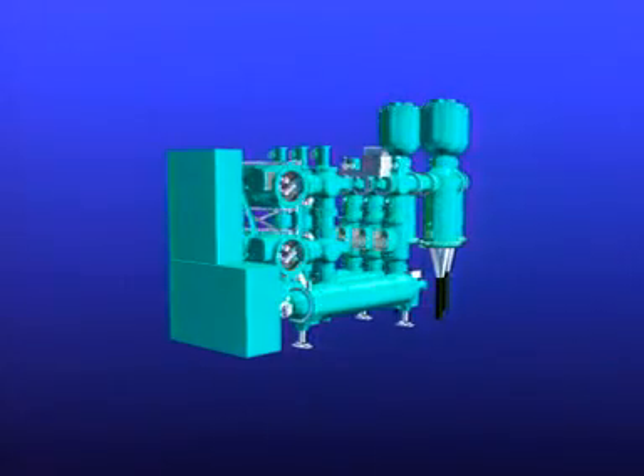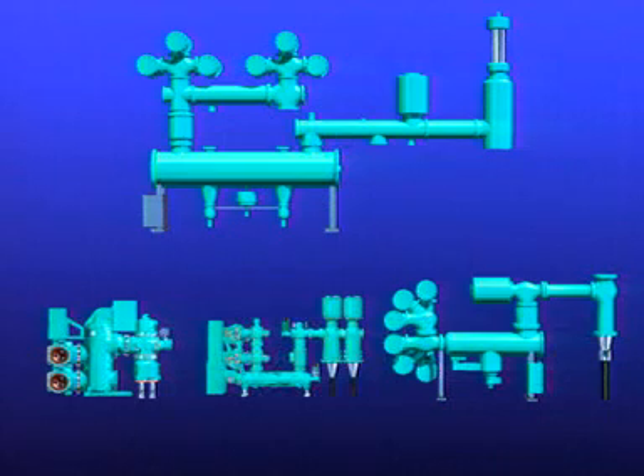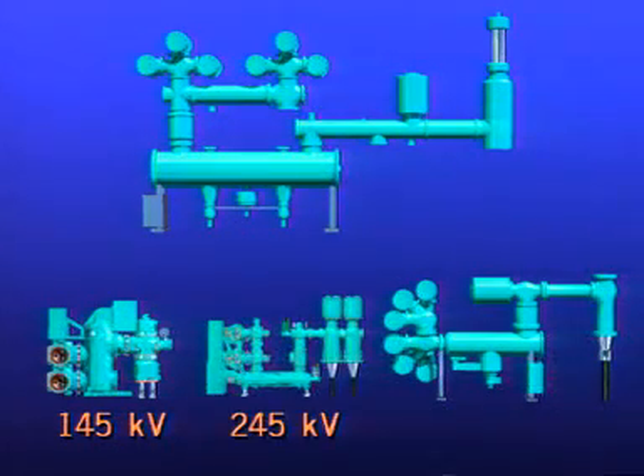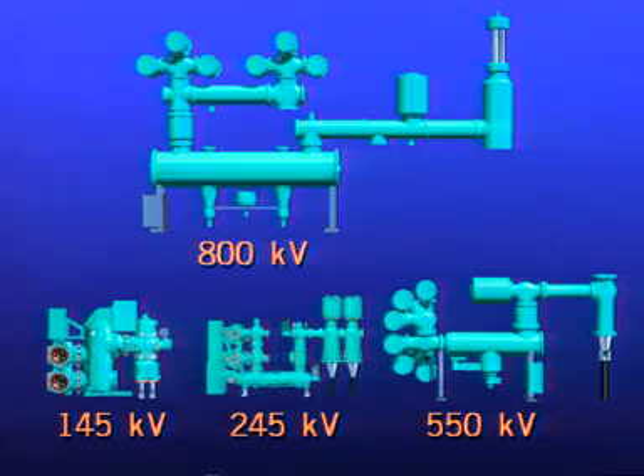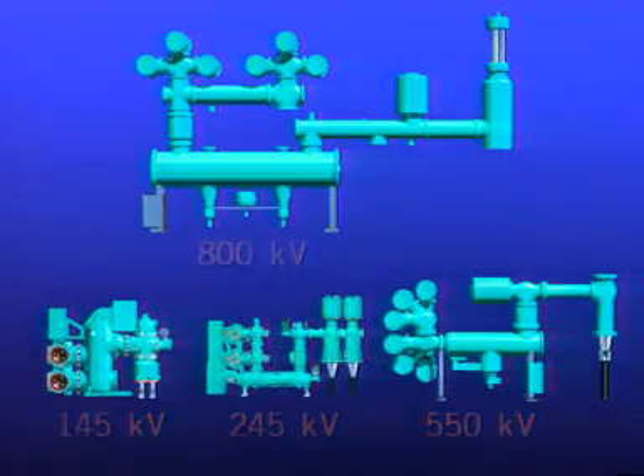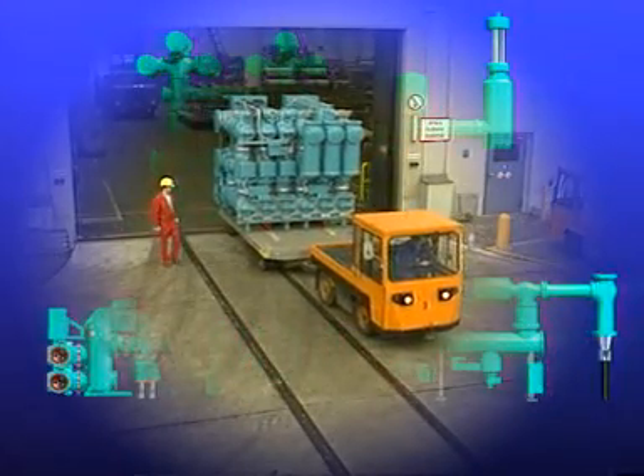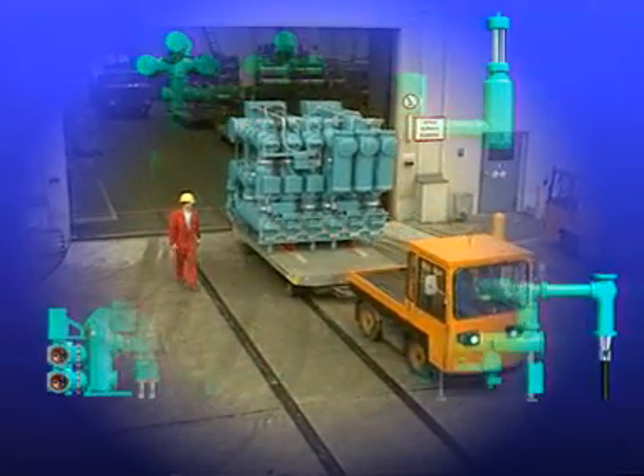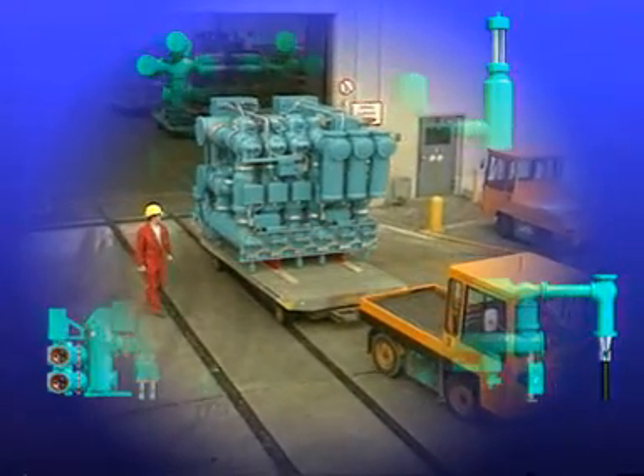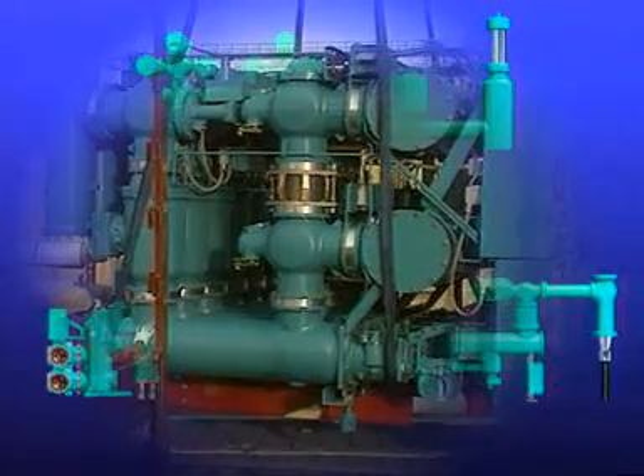It is part of the extensive product range of gas-insulated high-voltage switchgear available from Siemens. This ranges from the 8DN8 for a rated voltage of up to 145 kilovolts, through the 8DN9 for up to 245 kilovolts that you have just seen, and the 8DQ1 for up to 550 kilovolts, to the 8DR1 for 800 kilovolts. Siemens has installed more than 6,000 gas-insulated switchgear bays since 1968. At the same time, the technology and housing shapes have been constantly enhanced and perfected.